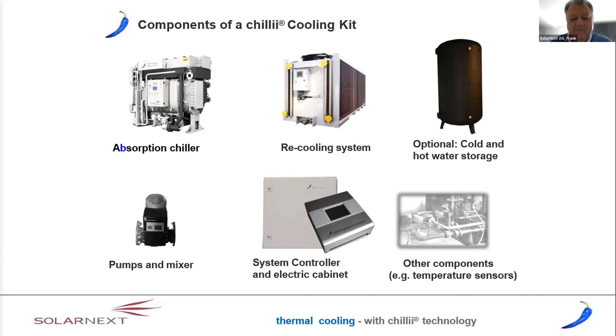The main used machine is the first one, a hot water absorption chiller, which is a single effect machine. It runs with driving temperature from 80 to 120 degrees Celsius, with delta T of 10 to 40 K. For example, you can run 90/70, 90/60, or 90/50. Cooling capacity is 30 to 2000 RT, meaning 105 to 7000 kilowatts per module, and the COP thermal is 0.82.